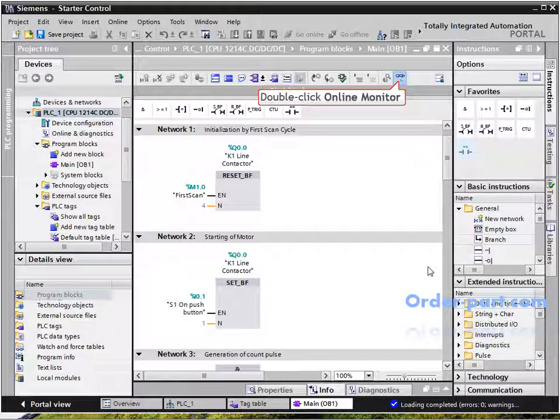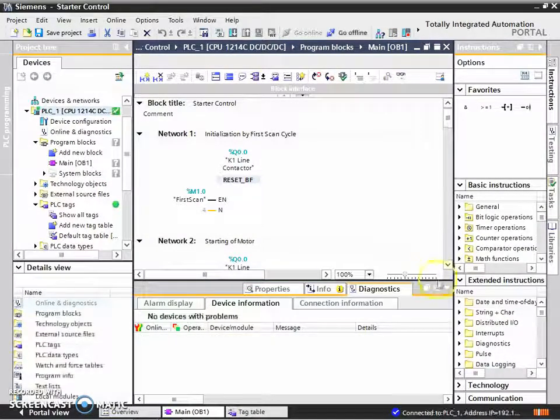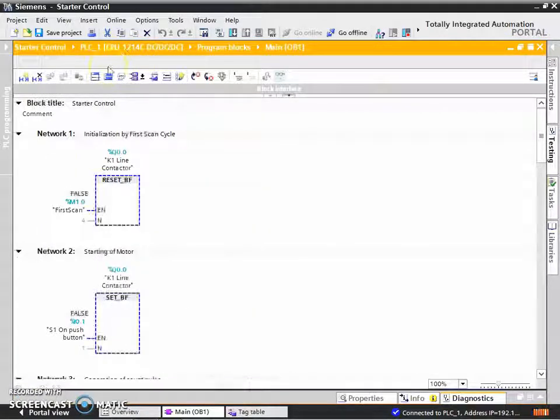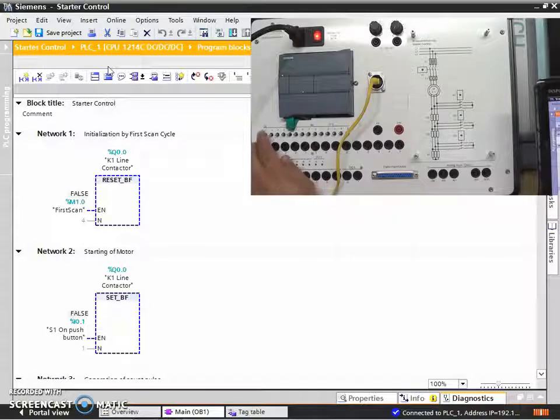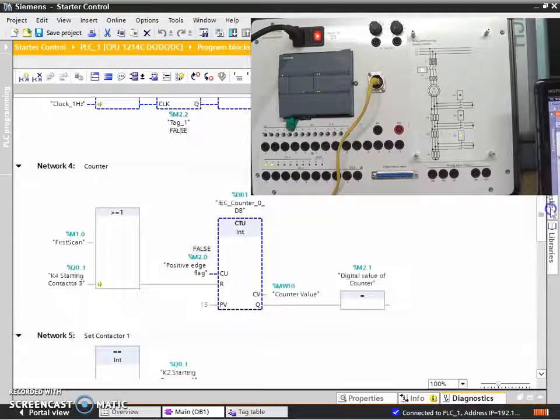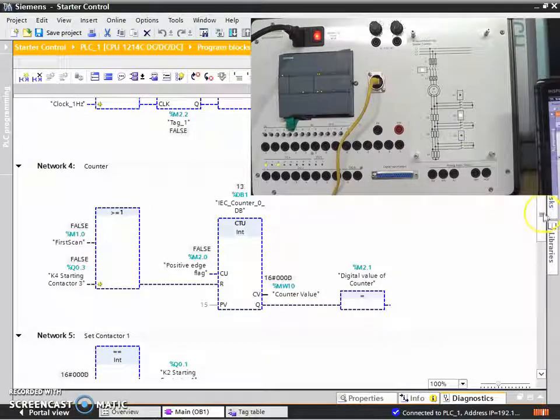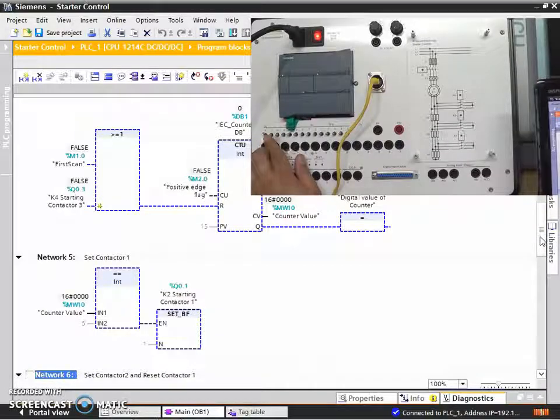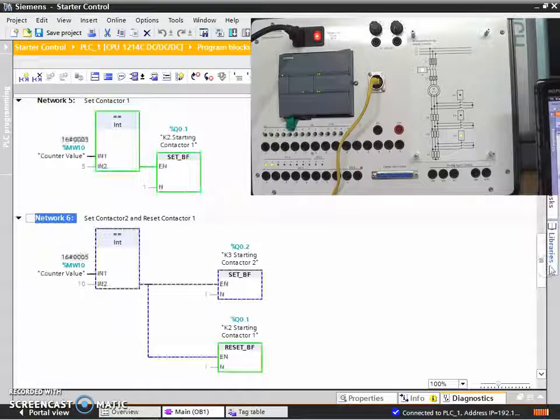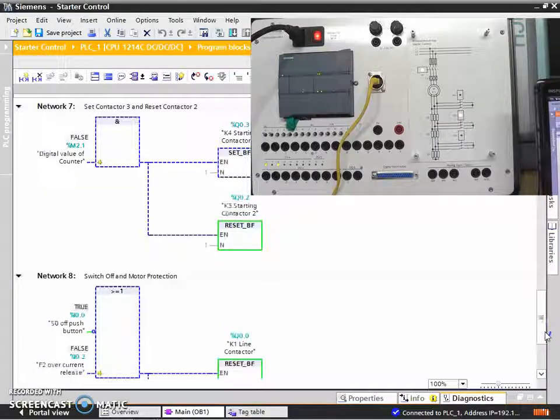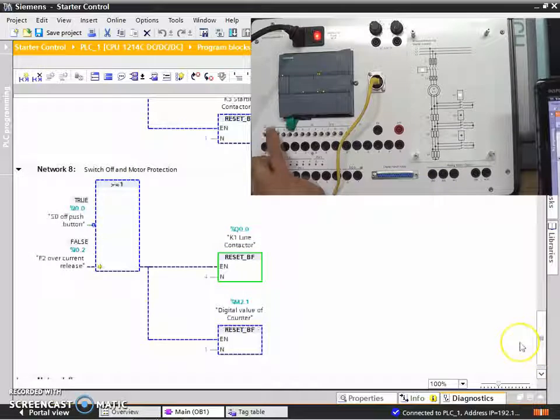Click on Online Monitor to view the actual position in the PLC. Click the arrow for a larger view. Here you can see the synchronized hardware and software view. Start the motor using I0.0 and I0.1. In Network 3, the one-second pulse is generated by M0.5. The counter increments to 15 and then resets from the K4 starting contactor. The program repeats again to give a clearer picture of the contactors in operation.